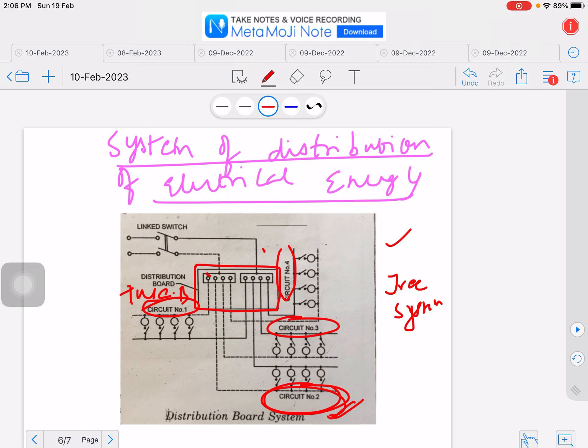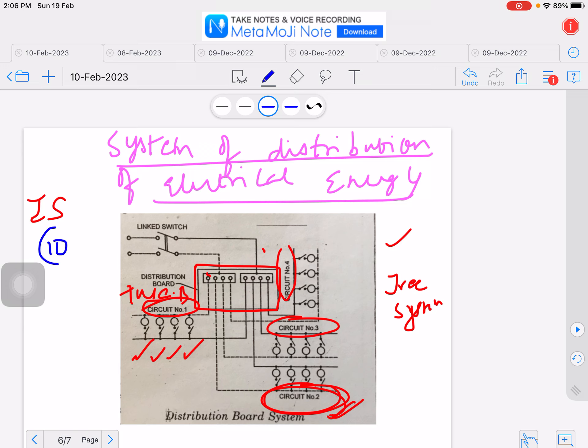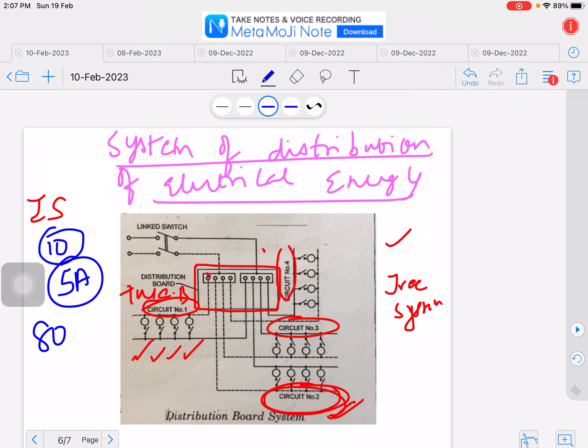If you are going to connect two or more circuits, each should consist of fewer than 10 lamps. According to the IS standards, in one sub circuit only 10 points are to be connected — this is the maximum load. A 5-amp socket can be included, and a maximum load of 800 watts should be restricted in each circuit. That is why in each circuit shown there are just 4 lamps — it could be less than 10, up to 10 points.